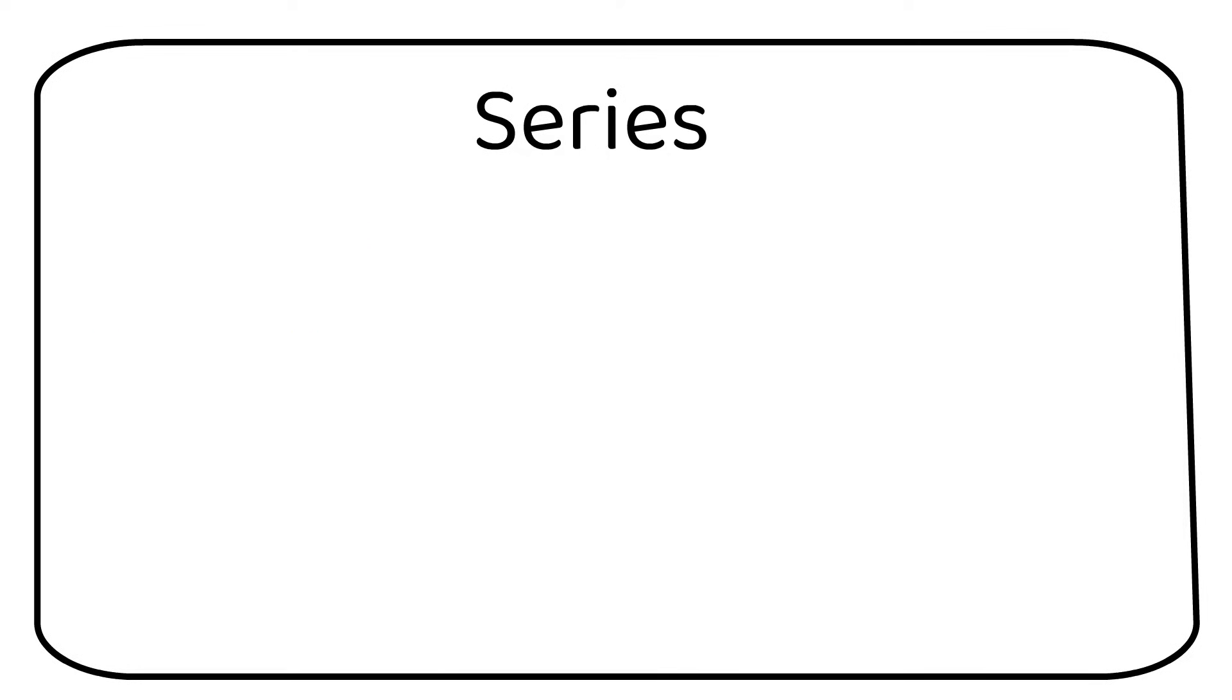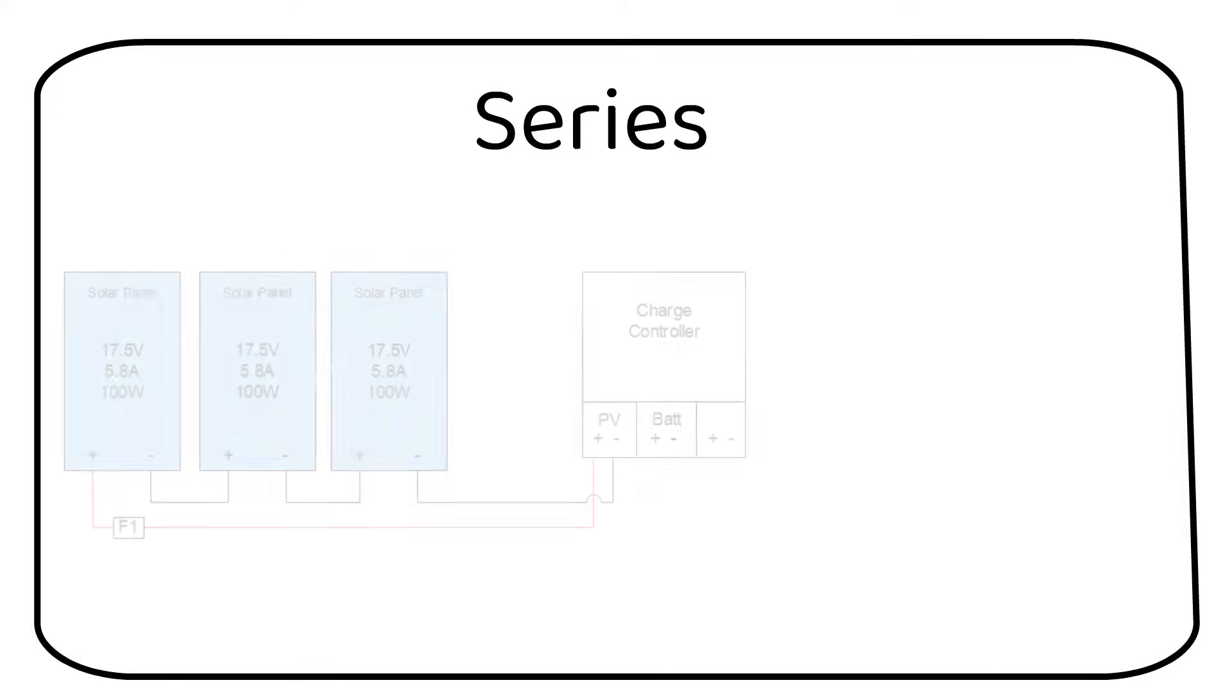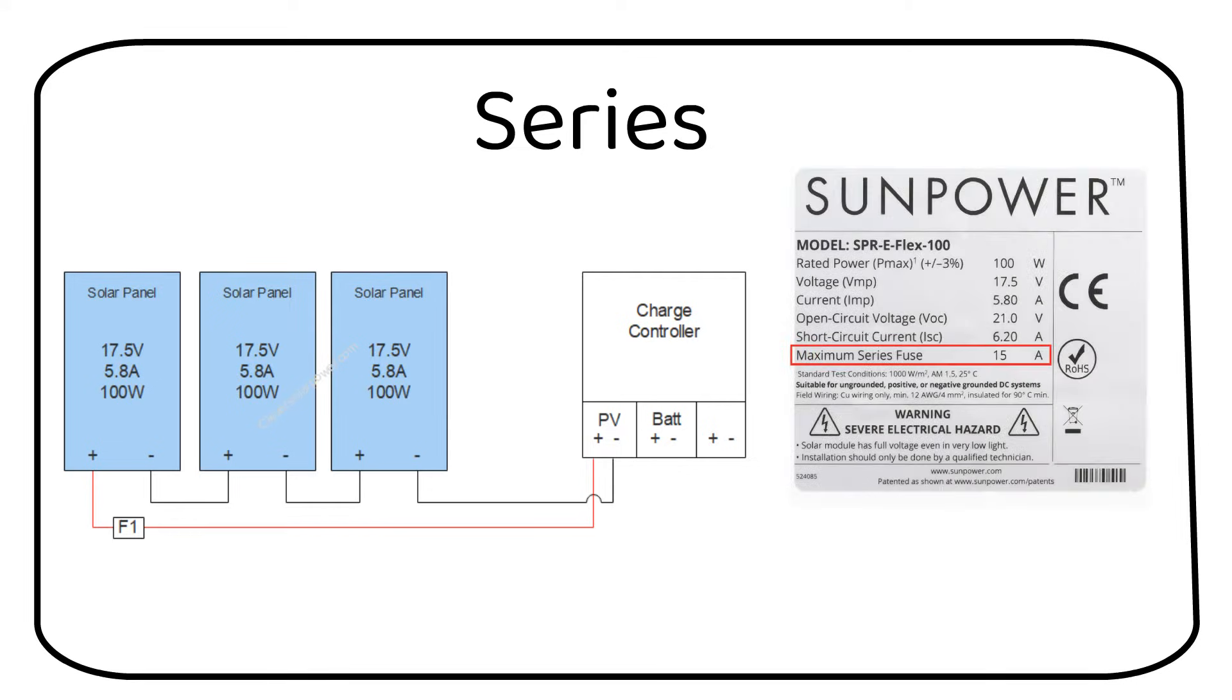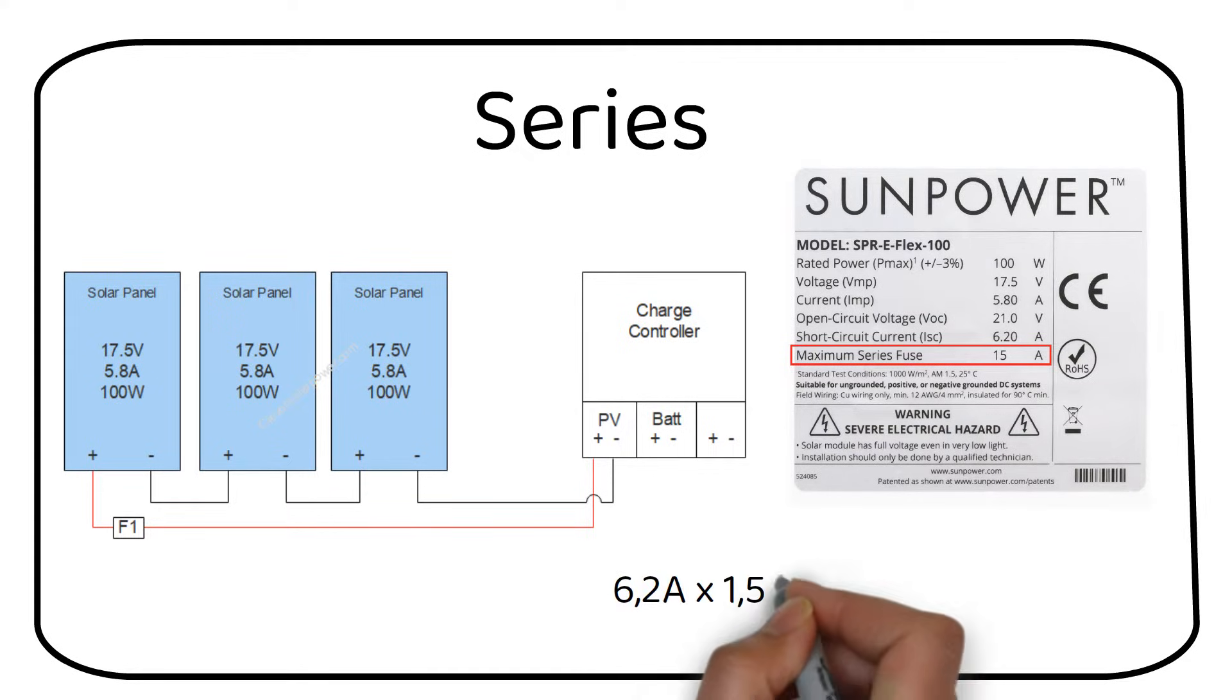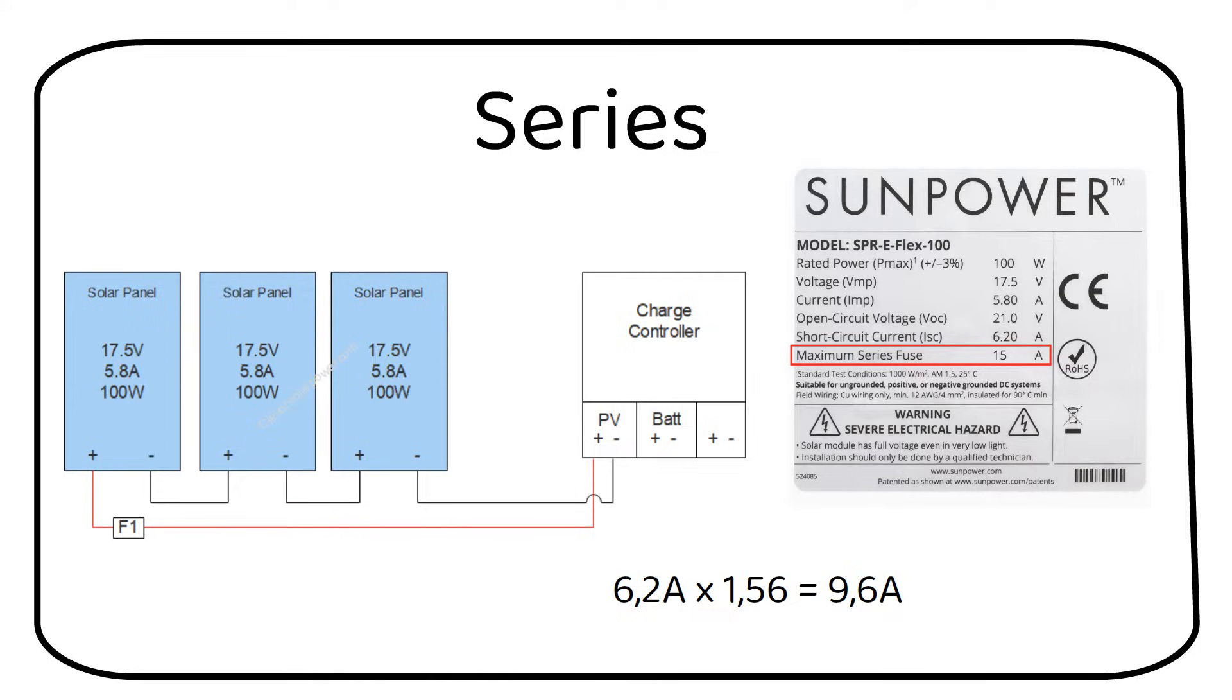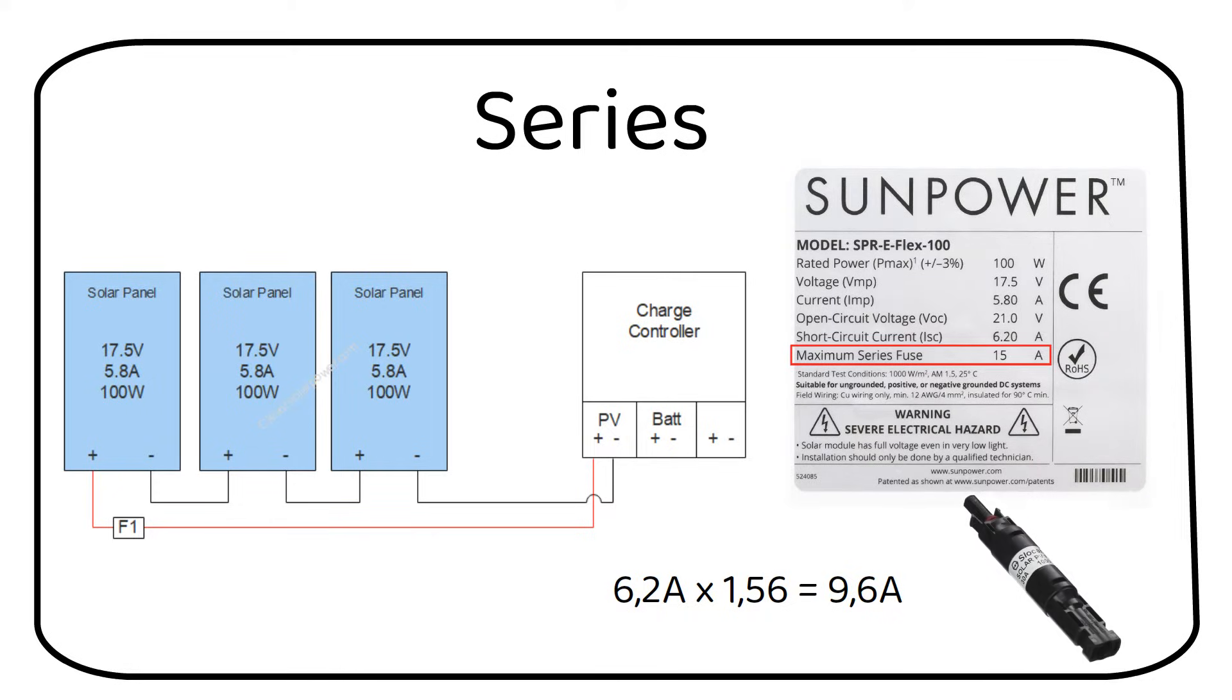Most of the time you will be wiring your panels in series. This is because MPPT charge controllers have a high input voltage and it's cheaper to wire them in series. In that case you only need to have one fuse on a positive wire coming from the solar panels. The maximum fuse size will be indicated on the back of the solar panel. If we use the formula ISC times 1.56 to calculate the minimum fuse size, it will be 6.2A times 1.56 equals 9.6A. In this case I would use a 10A fuse. We can use a general inline MC4 fuse.